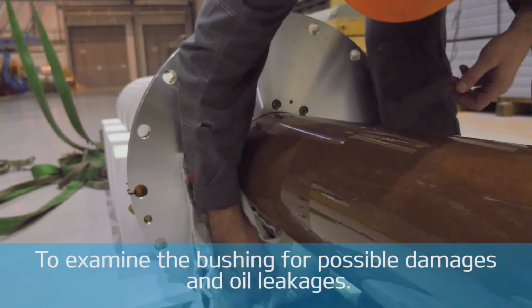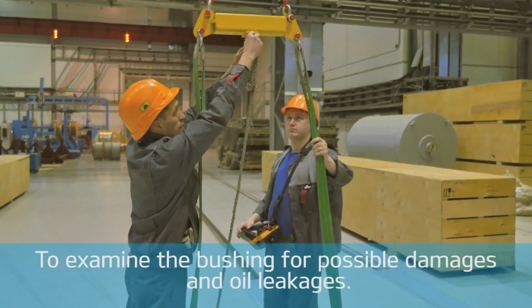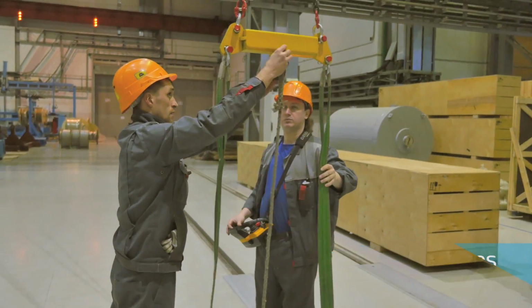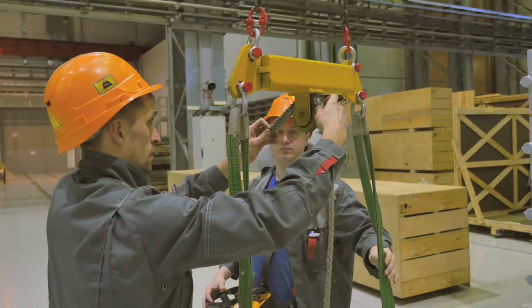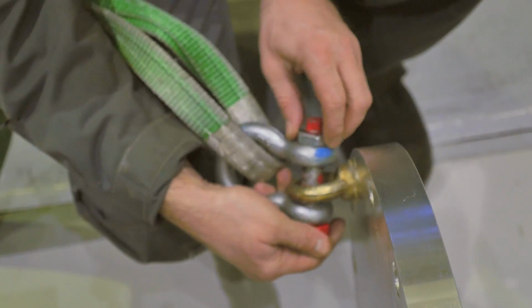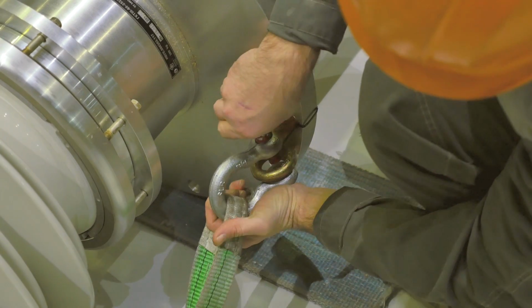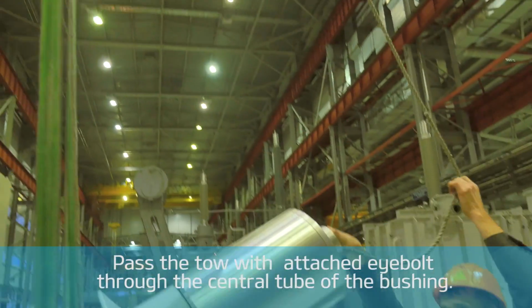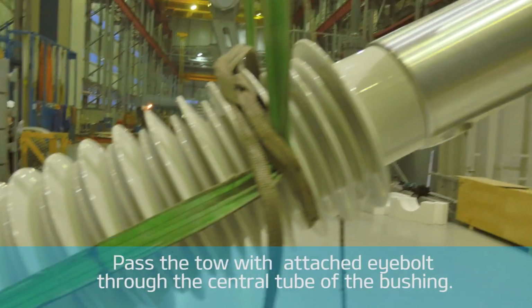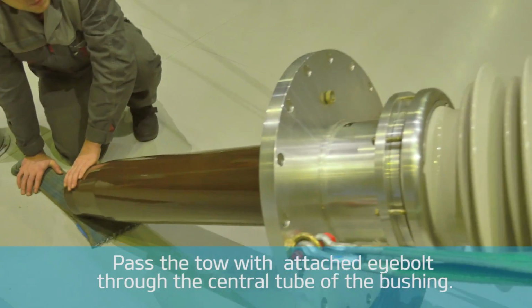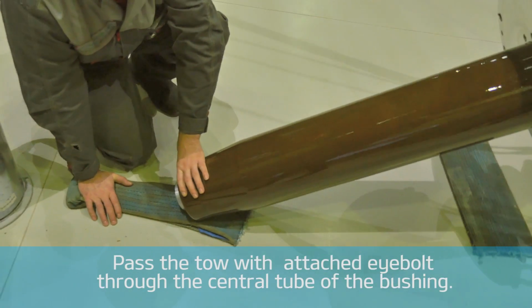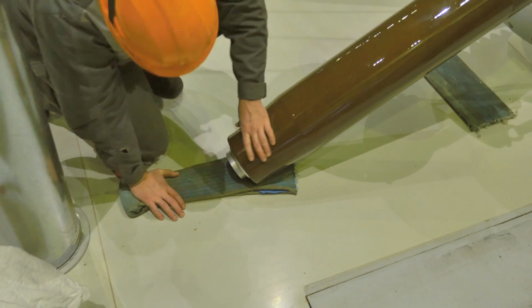The setting of the bushing to a vertical position does not differ from the process described for the bottom terminal bushing either. However, for draw lead type bushings, there is an extra operation to be done. It is required to pass the tow with attached eye bolt through the central tube of the bushing. The tow will be later used for drawing through the contact pin with soldered-in transformer tap lead.